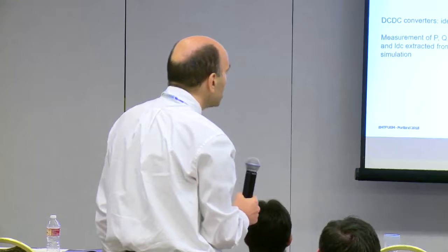You can use a partially selective, fully selective, or non-selective strategy. Normally, you use a rate of change of voltage, a ROCOV strategy. It's just local measurement, but there are disadvantages. So in simple terms, it's either ROCOV or differential. With differential, you need a pilot wire, and you have two signals at the two ends of the line, but it depends on the grid complexity and so on. So there's a lot of work still for this.